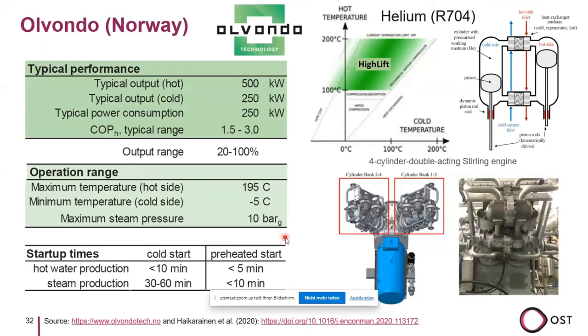Another company I'd like to mention, which some people may forget, is Olvondo. They have the high lift heat pump. It's running with a Stirling cycle, not with a Rankine cycle with evaporation and condensation. This one is all in the gas phase with helium, and they have this kind of cycle here on the top right. They have a four cylinder double acting Stirling engine, so there is the cold side and the hot side. With this principle they can achieve very high temperatures and also large glides, so large temperature differences on the heat source and sink.